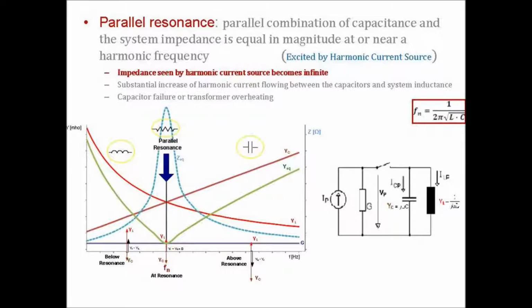So the big one is parallel resonance. That's excited by a harmonic current source. So if you've got any currents on your system and they interact with the impedance, and the impedance becomes quite large, you can have significant voltage distortion. So what happens is typically your system, well, I'll show you the circuit first. You've got, as the name suggests, a parallel resonance. You've got an inductor and a capacitor in parallel. And it's excited by a current source, and it gives rise to an admittance Y_C equal to jωC, and Y for the inductor is 1 over jωL.